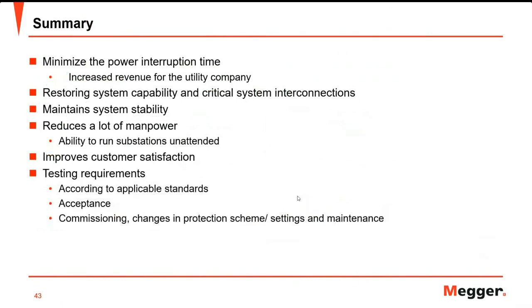In summary: reclosers minimize power interruption time. When we reduce interruption time, we increase revenue for the utility company, restore system capability and critical interconnections, maintain system stability, and reduce manpower — making it possible to run substations unattended. This can also improve customer satisfaction. Some testing requirements are required by applicable standards — for acceptance and commissioning, whenever there are changes in protection scheme or settings, and during scheduled maintenance.